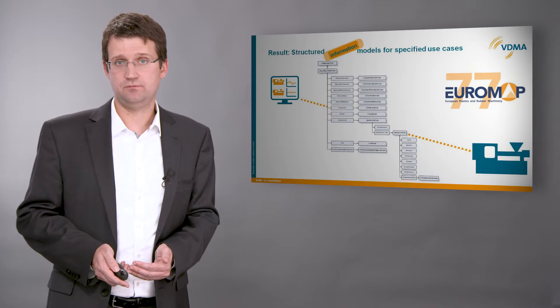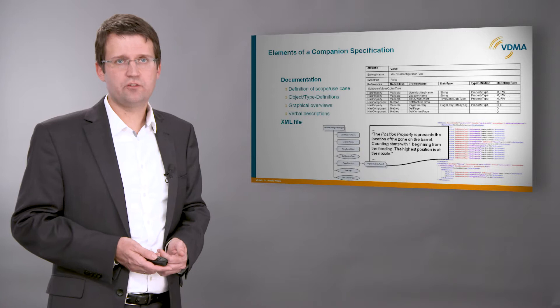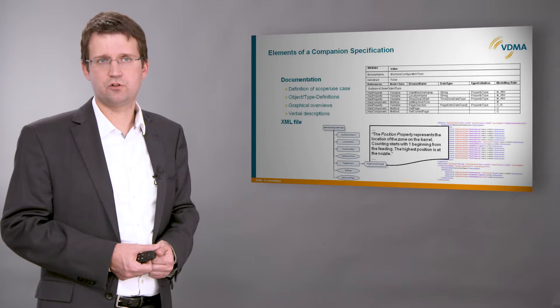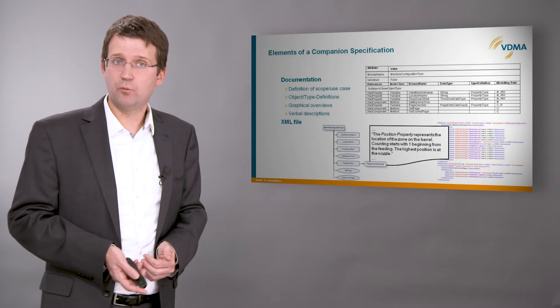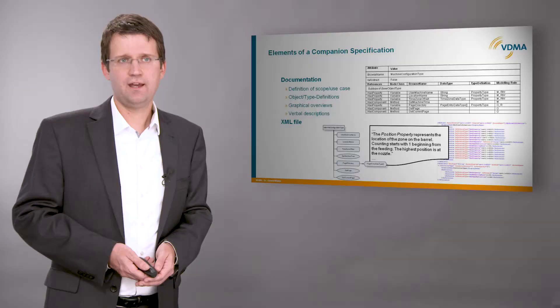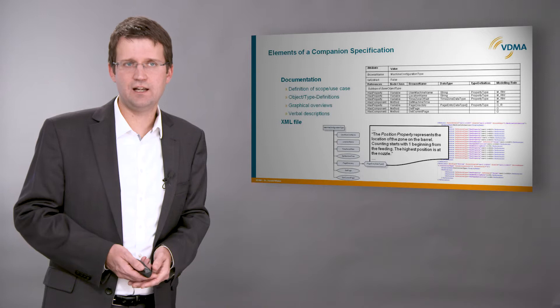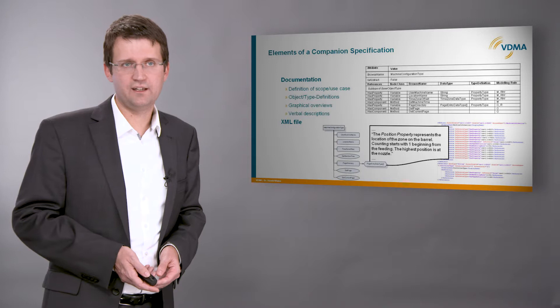When a companion specification is published, it consists of several elements. The first thing is always a clear definition of the concerned machine and the use case. The object types, methods, and events are formally described in standardized tables. These are accompanied by graphical overviews and verbal descriptions explaining the meaning of the described parameters. As a machine-readable component, for each companion specification an XML file with a model is provided. This can be used by developers for the creation of OPC UA servers and clients.